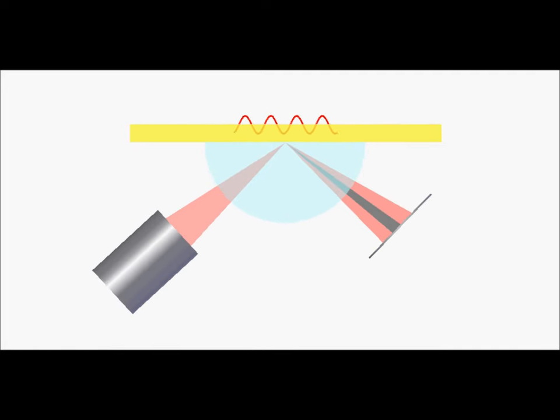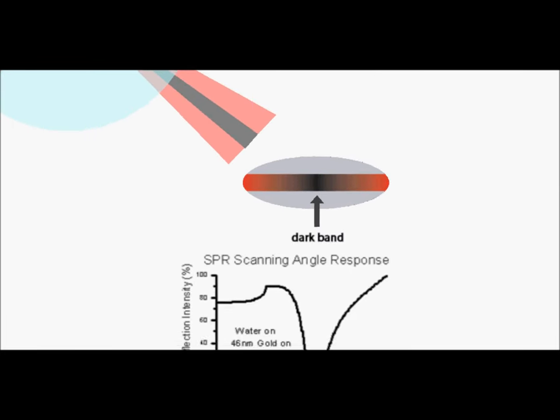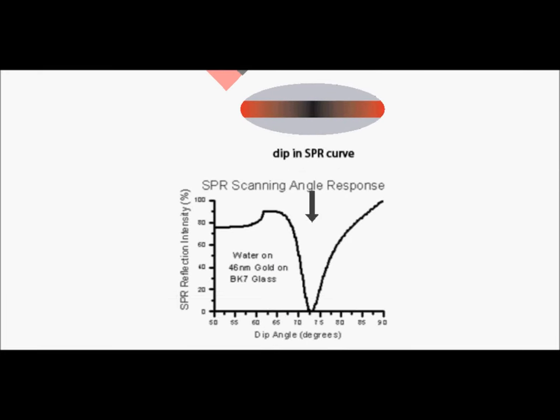The result is an intensity loss in the reflected beam, which appears as a dark band, and can be seen as a dip in the SPR reflection intensity curve. The shape and location of the SPR dip can then be used to convey information about the sensor surface.